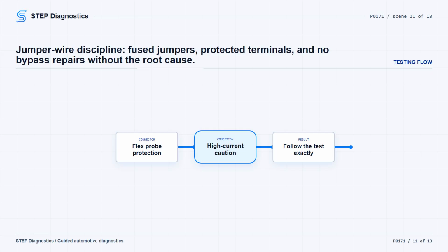If jumper wires are used, always use fused jumper wires. The recommended universal testing jumper wire fuse is 5 amperes or less, unless the load requires a larger fuse rating. Use flex probes or equivalent to protect terminals, but do not use flex probes to carry high current greater than 5 amperes. Follow the test directions carefully with jumpers, and never repair a circuit by adding a parallel wire until you understand why the original circuit failed.